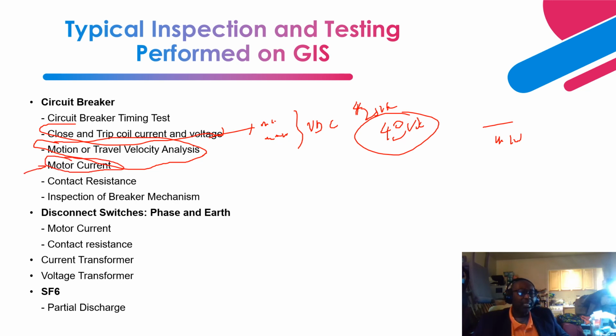Basically, the current drawn by the motor is also tested. That is very important, because if the motor draws high current, that tells you there's an internal short in the motor. In addition to that, insulation resistance testing is performed for the motor to make sure that the motor insulation is intact and the integrity of the insulation is high. Next is contact resistance.